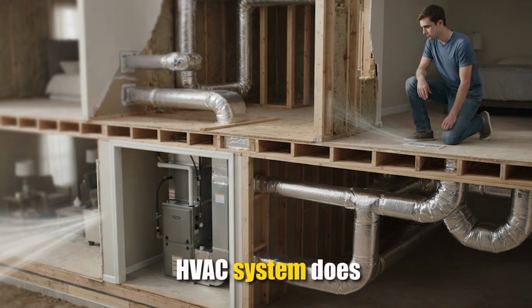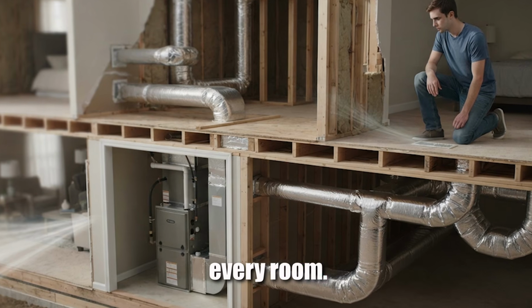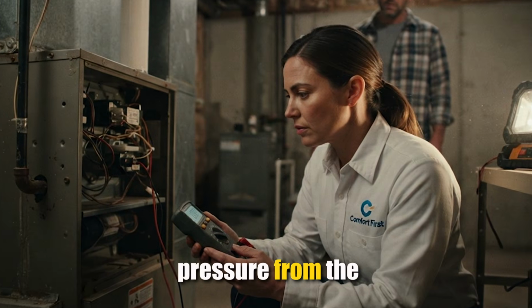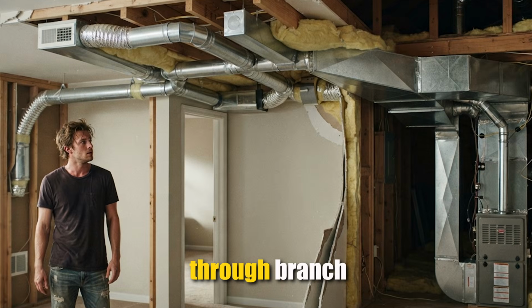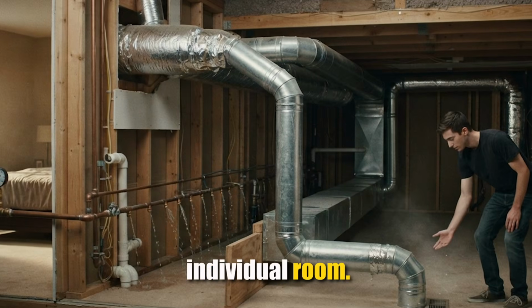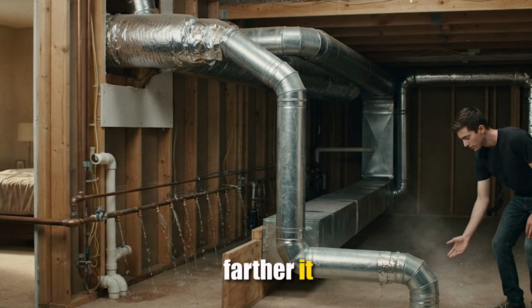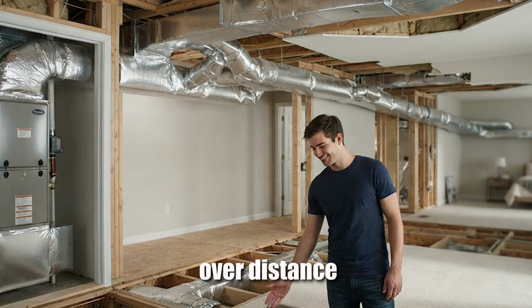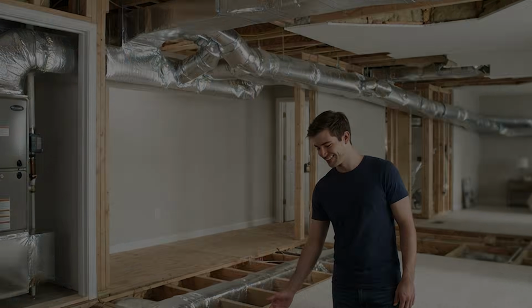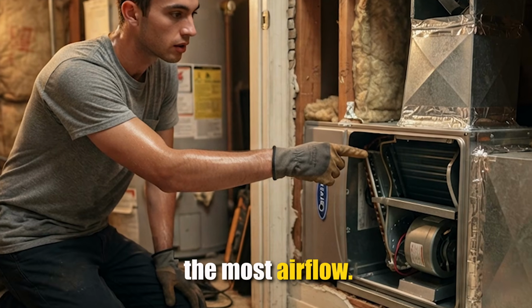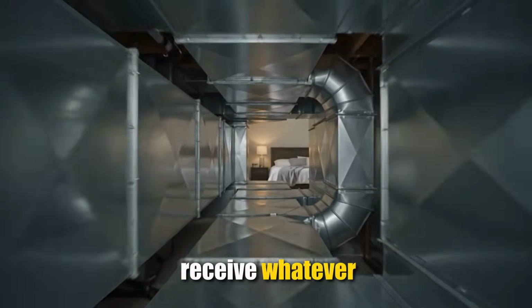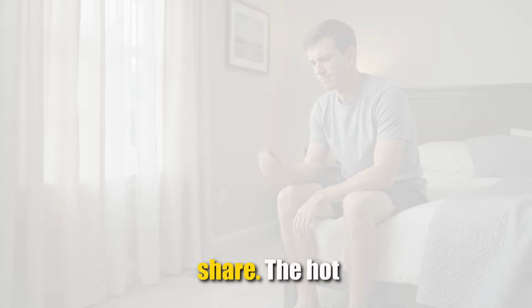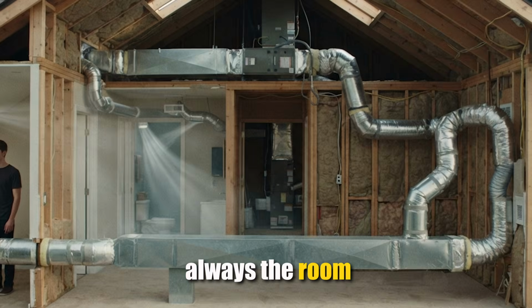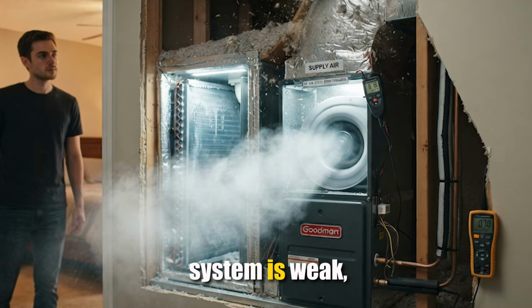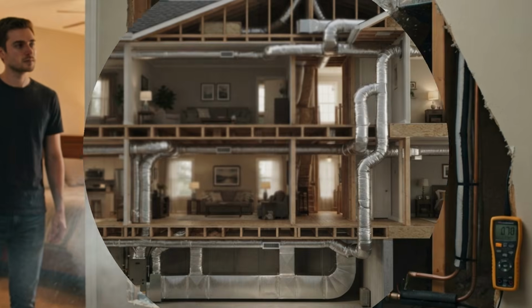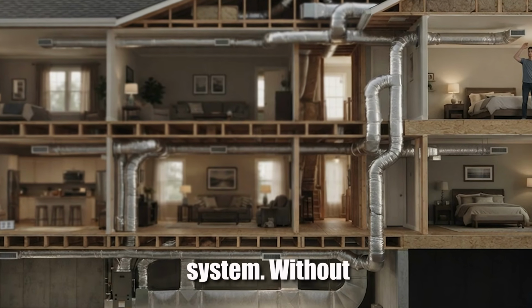Your HVAC system does not push the same amount of air to every room. It pushes air at a specific pressure from the air handler through a main trunk line and then through branch ducts that split off toward each individual room. And just like water pressure drops the farther it travels through pipes, air pressure drops over distance through ductwork. The rooms closest to the air handler, the rooms at the beginning of the duct run, receive the most airflow. The rooms at the far end of the system receive whatever pressure is left after the closer rooms have taken their share. The hot room in your house is almost always the room at the end of the longest duct run. Not because your system is weak, because pressure drops over distance. Physics. Every home, every duct system, without exception.